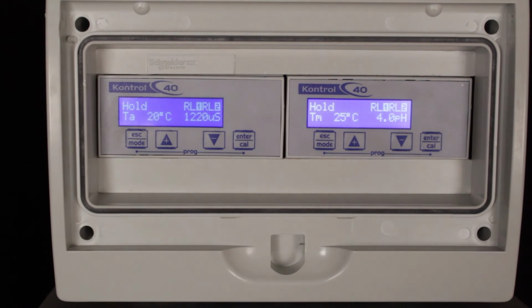Interlocking a flow switch or level switch. A flow switch or level switch can be connected to the controller. As soon as this function is enabled and there is no flow, the controller will indicate hold and the outputs will be disabled. As soon as flow or the right level is detected, the hold sign disappears and the controller will begin to operate again.